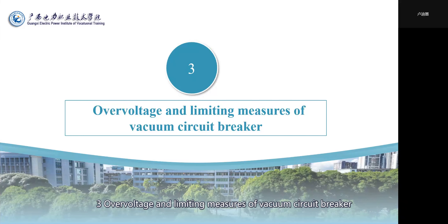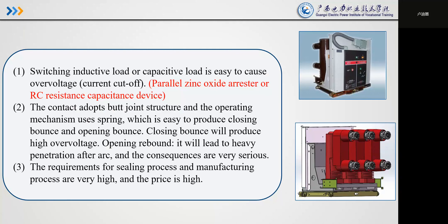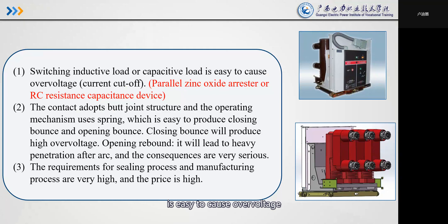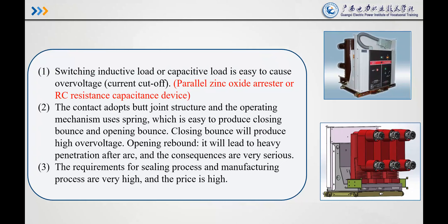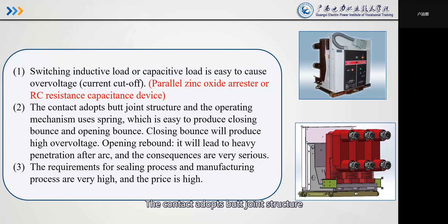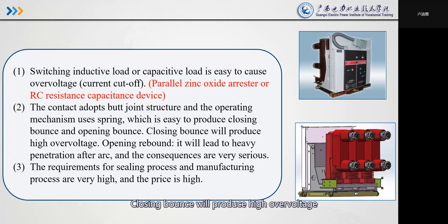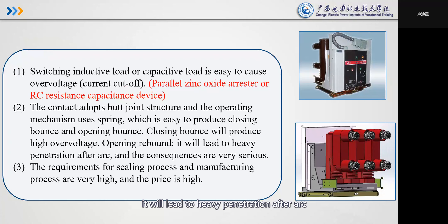Section 3: Overvoltage and limiting measures of vacuum circuit breakers. Switching inductive load or capacitive load is easy to cause overvoltage. Causes include: (1) current cut-off; (2) parallel reignition. The contact adopts a butt joint structure and the operating mechanism uses springs, which is easy to produce closing bounce and opening bounce. Closing bounce will produce high overvoltage; opening bounce will lead to heavy re-ignition of the arc, and the consequences are very serious.